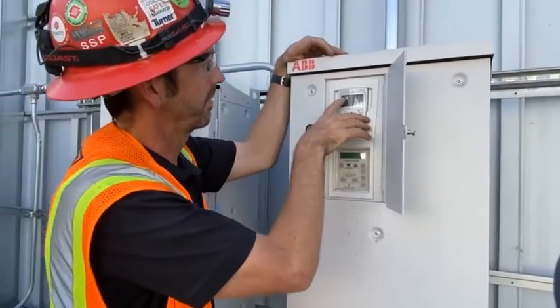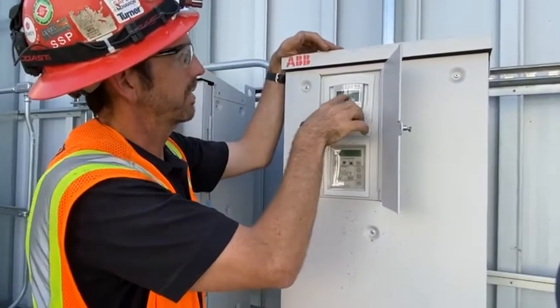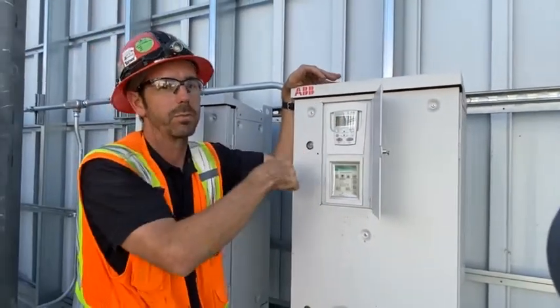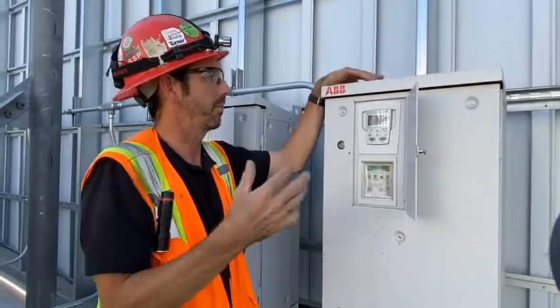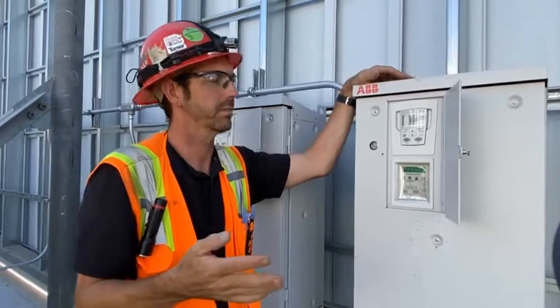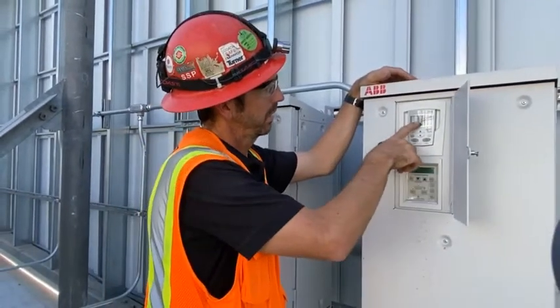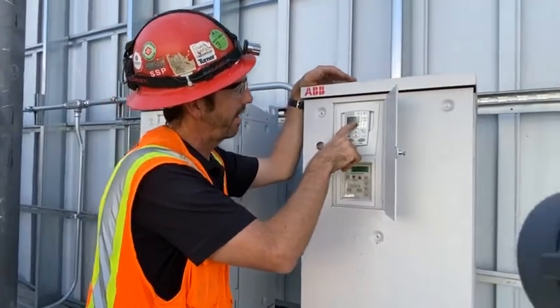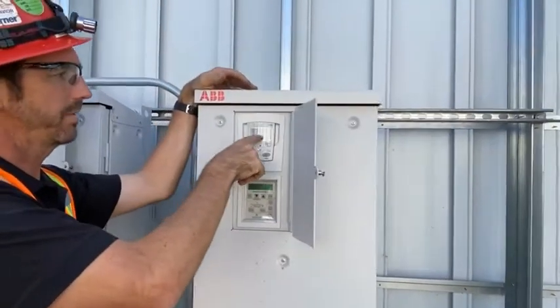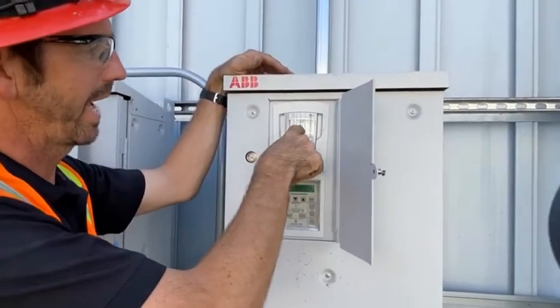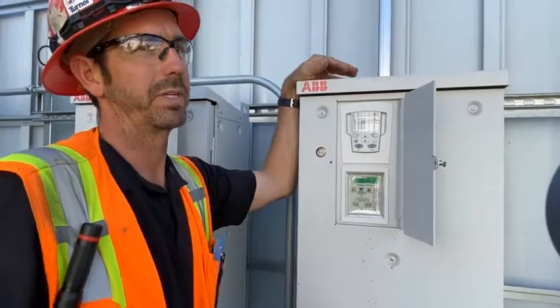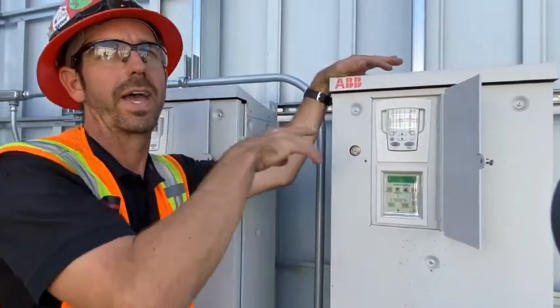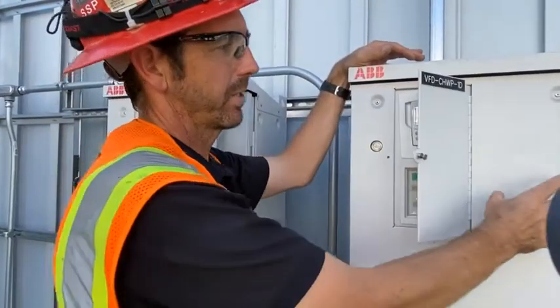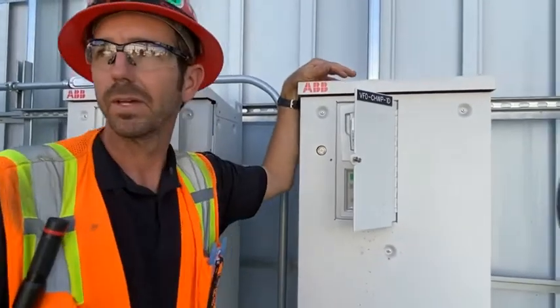And that's in the upper left-hand corner. We'll see percent speed. Percent speed over here will be out of 60 hertz. Pumps are always run to 60 hertz. On the line below that, we have amperage. Right now it's off, so it's reading 0. And then below that, it's volts DC, which will be your speed reference signal that comes in on that analog input that I showed you was landed on the drive side of this over here. Okay?